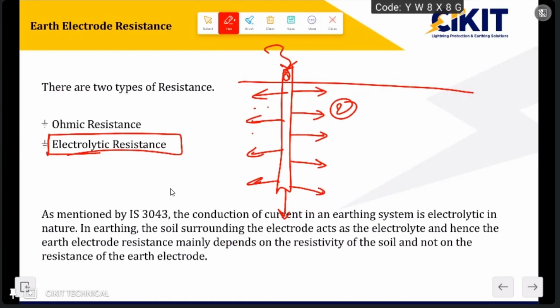So if you take this earthing, depending upon the soil resistivity, the earth resistance value will be different. So with one earth electrode of the same dimension and the same earthing compound, we cannot ensure that if you install this particular product on any kind of soil, you can achieve the same values. That is not at all possible, and we cannot do any magic for maintaining the same value.